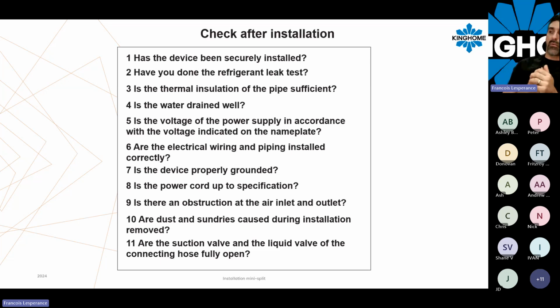You have checked the power supply in accordance with the nameplate, so we will not run into some sort of electrical problems in a couple of years from now. The system is also properly grounded. This is very important because we are using a lot of communication lines with those units, between the outdoor and indoor unit, but also directly at the outdoor unit, there's a bunch of communication between everything. So it needs to be grounded to make sure the communication can flow without any restriction.